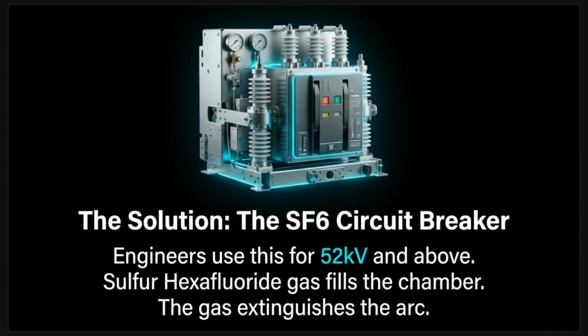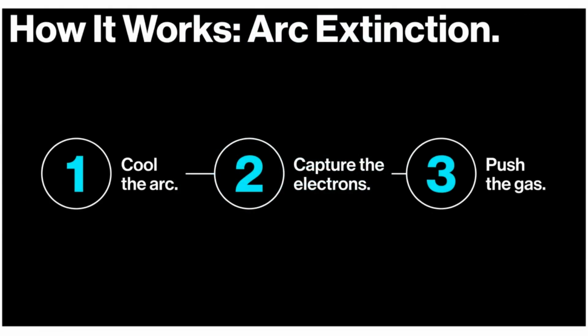The solution is the SF6 circuit breaker, used for 52 kilovolts and above. Sulphur hexafluoride gas fills the chamber, extinguishing the arc. Arc extinction works in 3 steps. Cool the arc, capture the electrons, and push the gas.